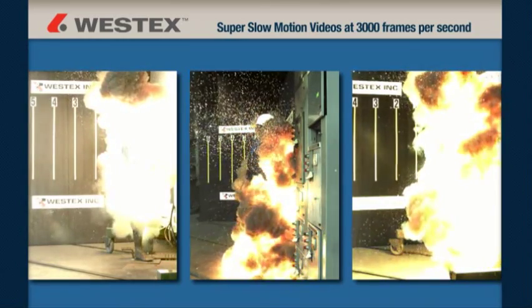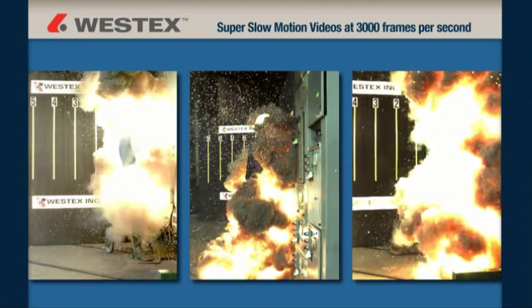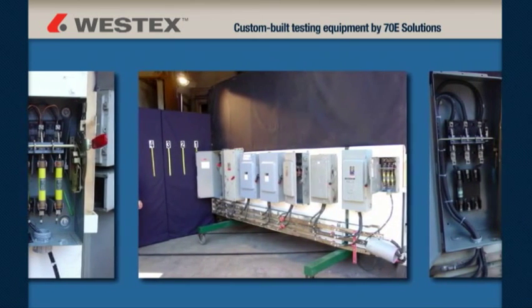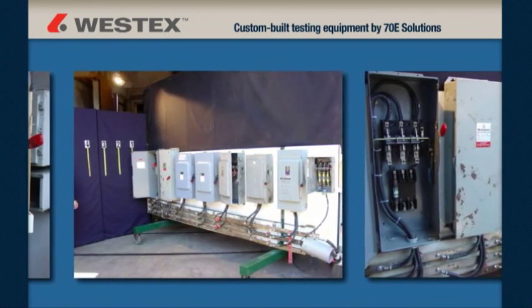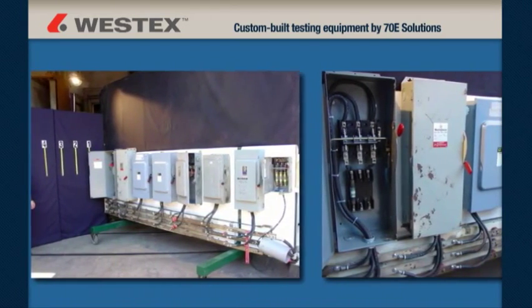This technology allows an unprecedented look at industrial arc flash and an outstanding look at the projection of the molten metal. Westex worked with Mike Wright of 70E Solutions to custom build a one-of-a-kind sled with a common 480-volt bus at the bottom and 30, 100, and 200 amp disconnects installed above. We created the arc flashes by placing a tool or a wire across all three phases.